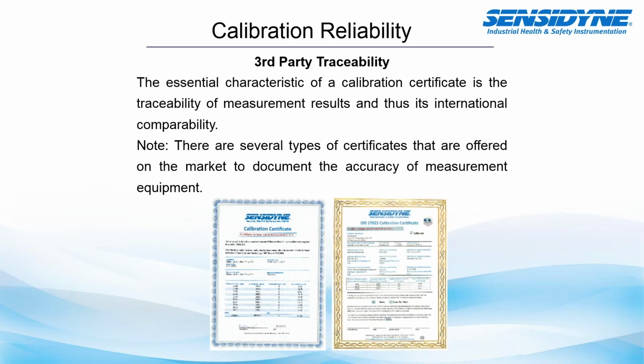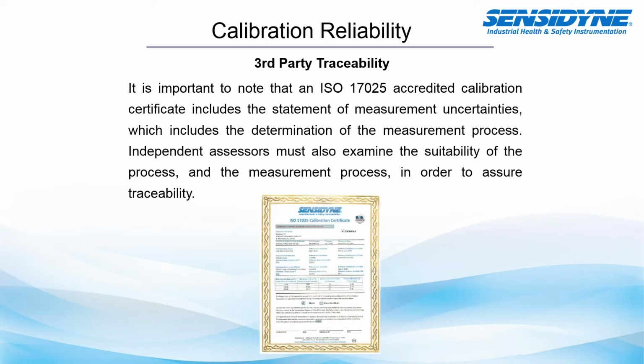The essential characteristic of a calibration certificate is traceability of measurement results, and thus its international comparability. So as I mentioned before, there are several types of certificates on the market used to document the accuracy of the measurement and the equipment. They're not all held equal. Note that a NIST calibration certificate is not necessarily an ISO 17025 calibration certificate, and that ISO 17025 certified calibration laboratories are typically held to a higher regard and deemed more reliable. So these certificates for the ISO 17025 contain a measurement of uncertainty, which the NIST certificates typically do not.